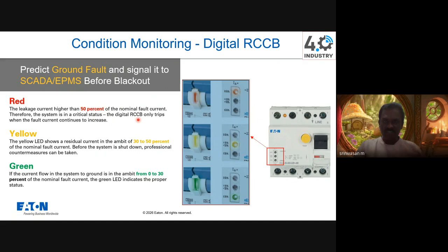But in our case, by having this digital RCCB, if the leakage current is between 30 to 50 percent, then we will have a local indication on the RCCB itself on the front fascia. Also, we have a dry type contact. We can signal it to the BMS or SCADA system, or you can use some kind of lamp or hooter in front of the board itself, giving an indication that the RCCB is going to trip after some time, so that we can take preventive actions well in advance. So this is one of the big advantages of having a digital RCCB.